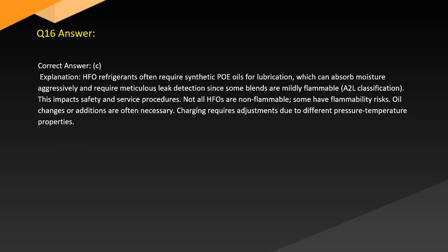Answer. Correct answer, C. Explanation. HFO refrigerants often require synthetic POE oils for lubrication, which can absorb moisture aggressively and require meticulous leak detection since some blends are mildly flammable. Check the A2L classification. This impacts safety and service procedures. Not all HFOs are non-flammable, as some have flammability risks. Oil changes or additions are often necessary. Charging requires adjustments due to different pressure-temperature properties.